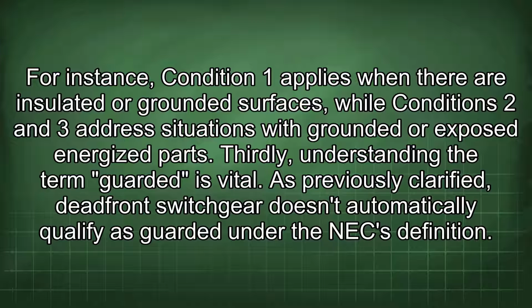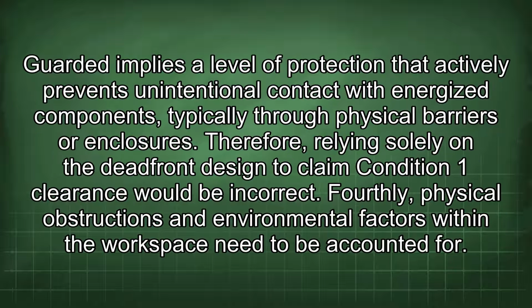Thirdly, understanding the term guarded is vital. As previously clarified, Deadfront Switchgear doesn't automatically qualify as guarded under the NEC definition. Guarded implies a level of protection that actively prevents unintentional contact with energized components, typically through physical barriers or enclosures. Therefore, relying solely on the Deadfront design to claim Condition 1 clearance would be incorrect.